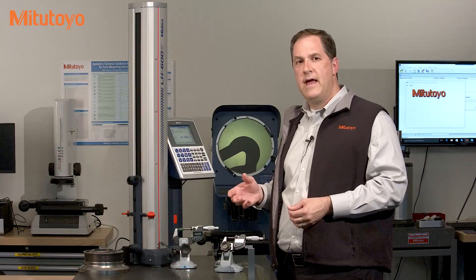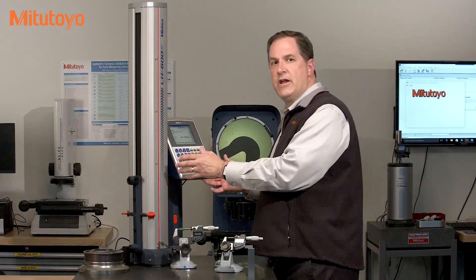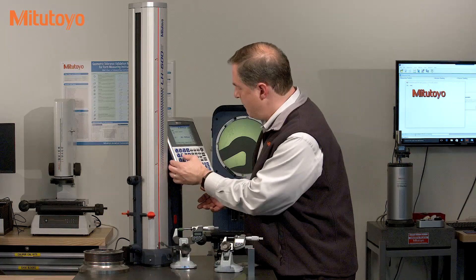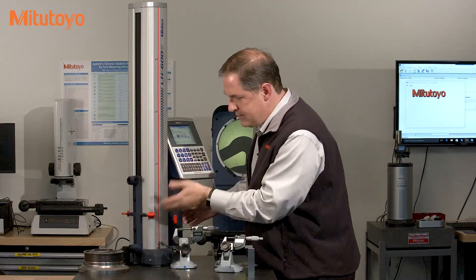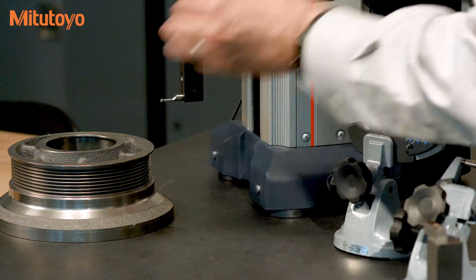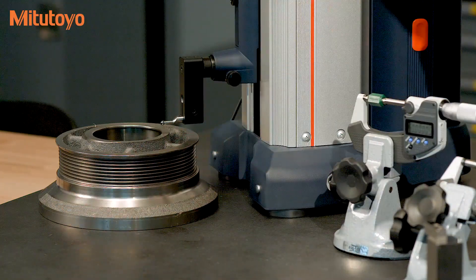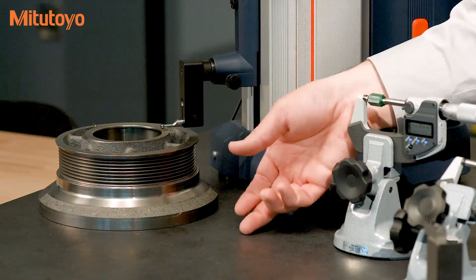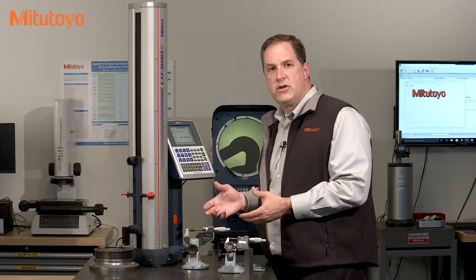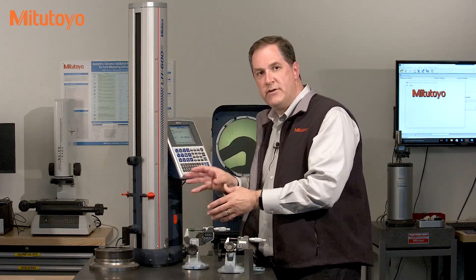We will start by looking at the everyday use of the measuring equipment. Say this linear height is used daily to measure some part like this. I'll measure on the surface plate here, then bring in the parts and measure this height. Whoever is using this measuring system wants to make sure the overall accuracy and quality of this measurement process meets their needs.